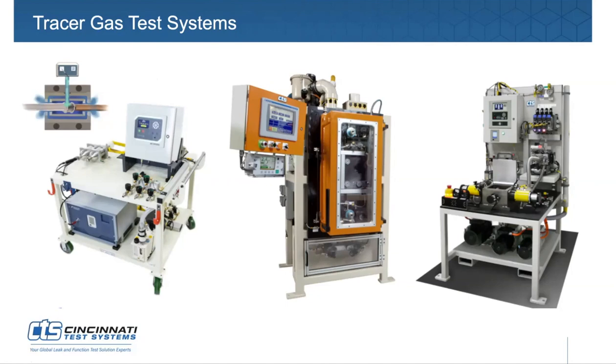That's a part tested within the orange chamber, and helium being tested for its concentration rate of rise in that chamber. It's also tested in a background of our atmosphere, which is 5 parts per million helium. 5 parts per million helium equates to a 1 times 10 to the minus 5 cc per second leak rate. And it's really low.